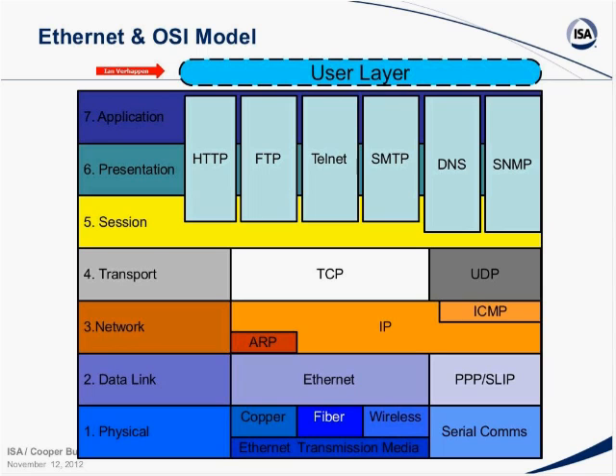The reason the OSI model is so important is that you can use multiple different layers of protocol on the same physical layer. So practically all the different bus protocols - Modbus, for example, is the one we've picked as an example. So you have Modbus RTU, which is basically the serial version of Modbus.